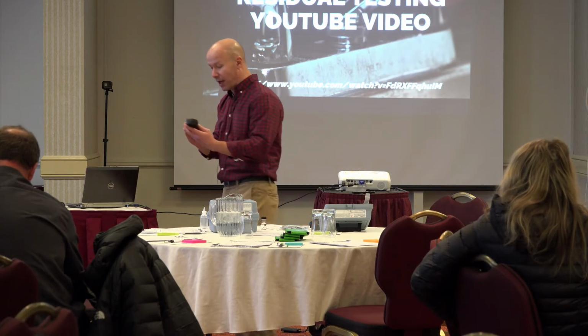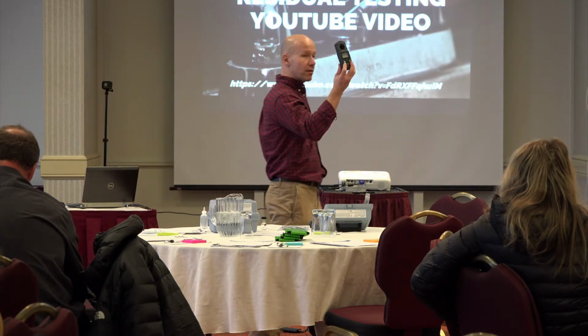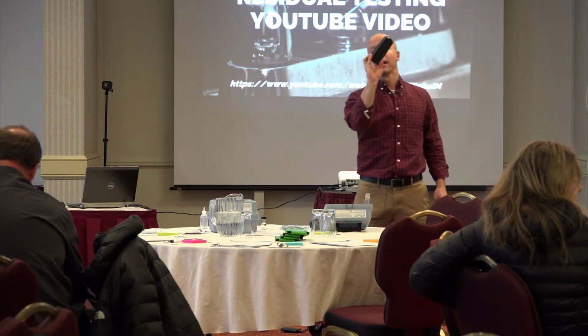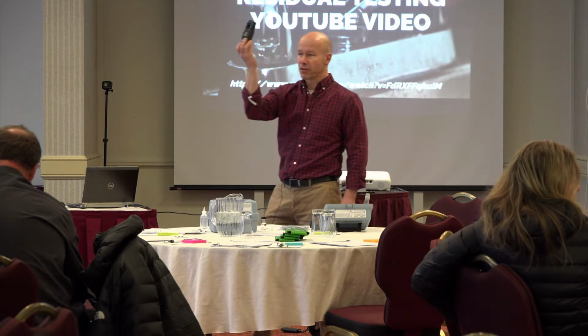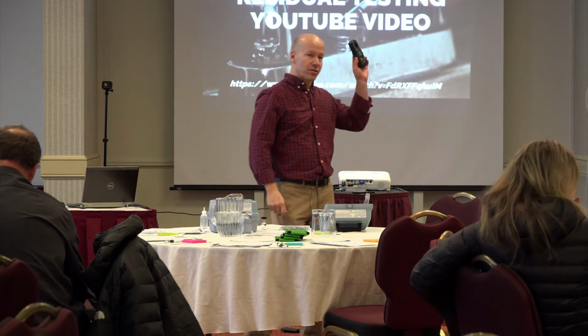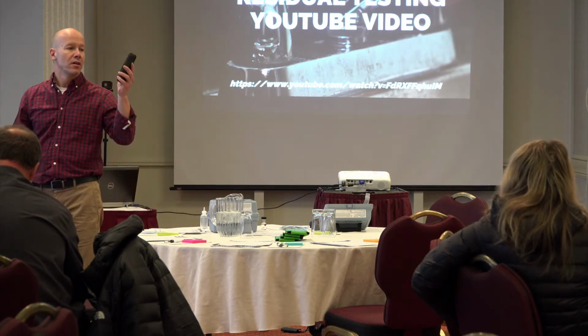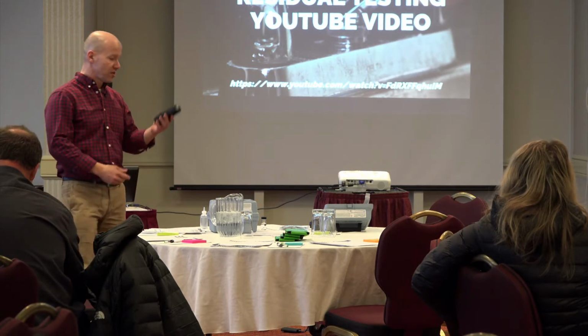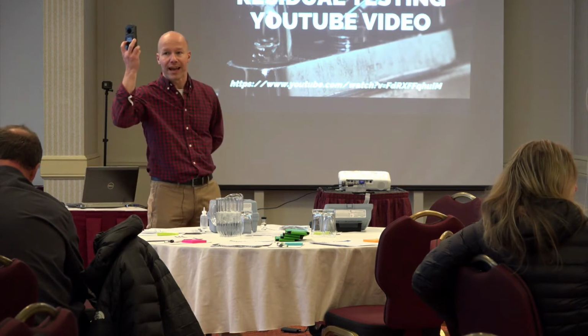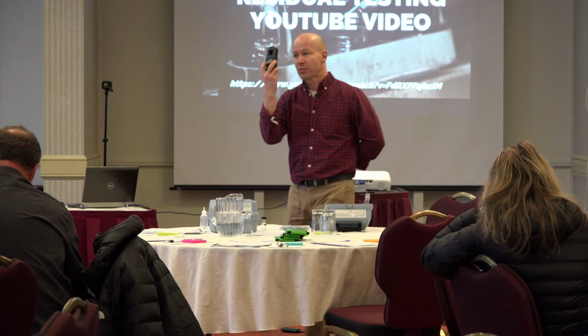In order to turn on our kit, you'll notice there's 4 buttons on our kit. We've got a green read button, a blue 0 button, a menu button, that's 4 little lines, and our power button. So we're going to turn on our power button. And what you'll see is whatever the last residual taken with this kit was, that's the one that pops up there. The first thing we're going to look for is, you can see on the top left of the display there should be a little triangle pointing at LR. That means you're in the low range. So that's the range we're going to test in first.